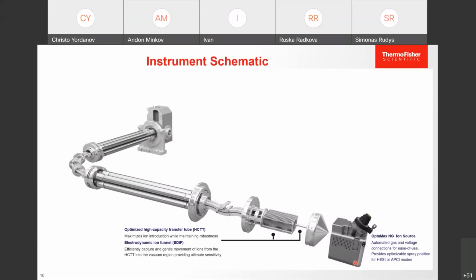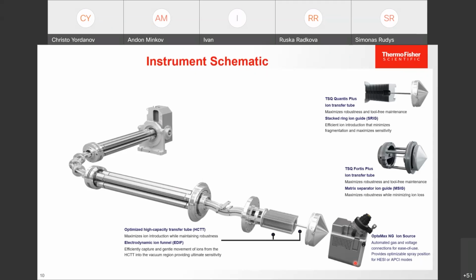The next part is ion optics. On the TSQ Altis instrument, we have a high capacity transfer tube with a wider bore to inject more ions and an electrodynamic ion funnel, which helps to focus this bigger amount of ions. On TSQ Quantis, we have S-lenses for improved sensitivity and robustness. And on the entry-level TSQ Fortis Plus, we have a matrix separation guide for maximum robustness.